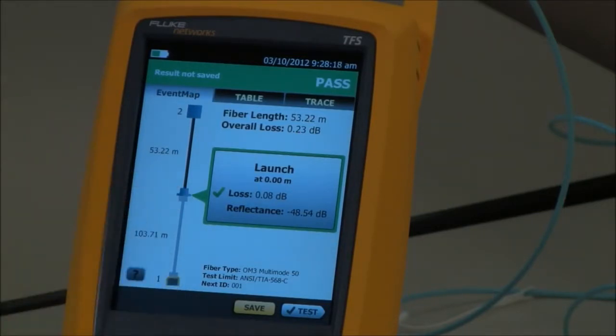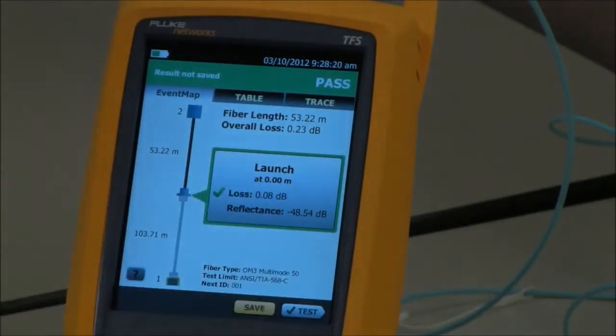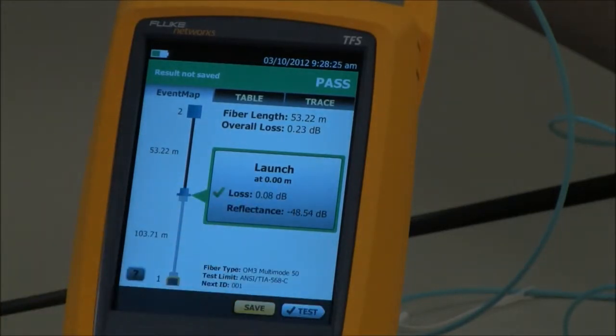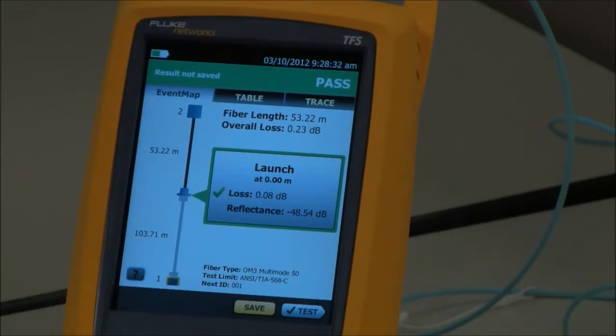I've connected in, and where I've connected in I have a fantastic loss of 0.08 dB and an awesome reflectance of minus 48.54 dB. Where minus 35 is good, minus 48 is even better.